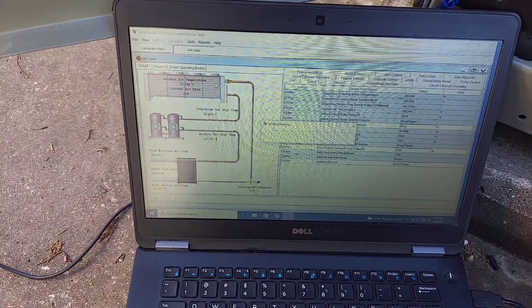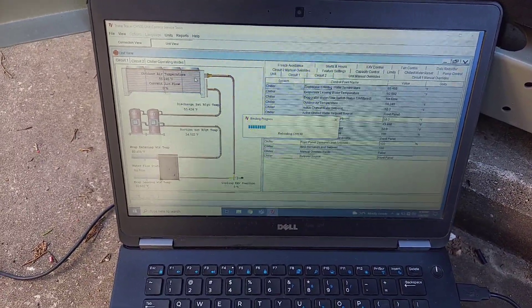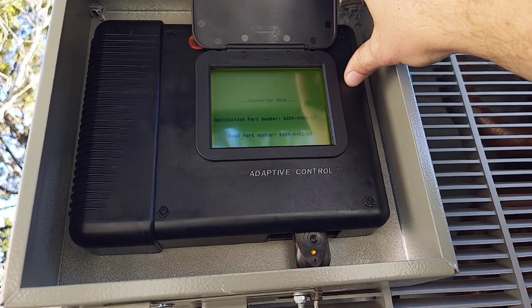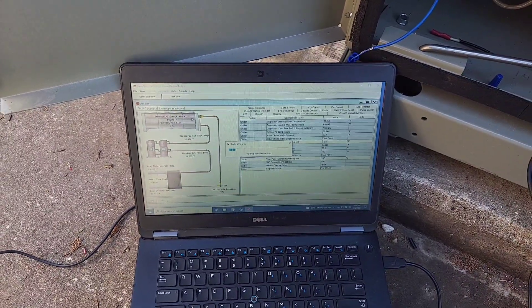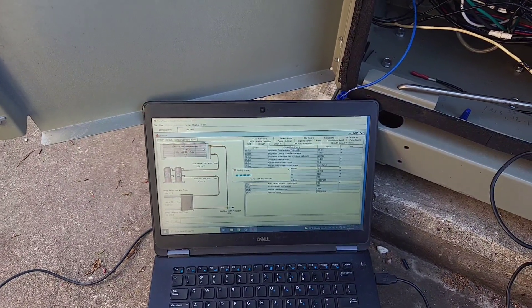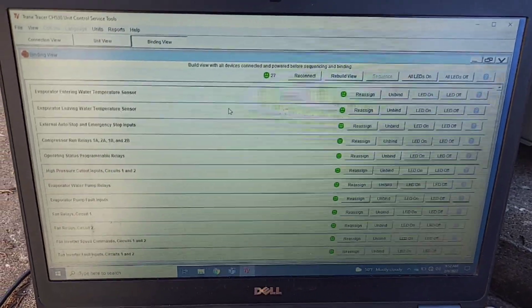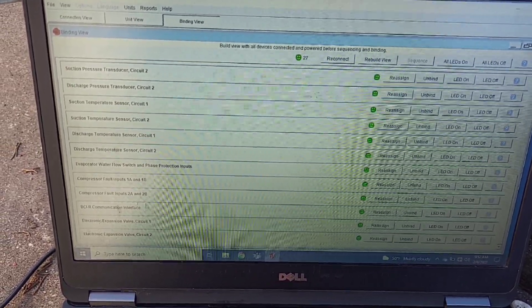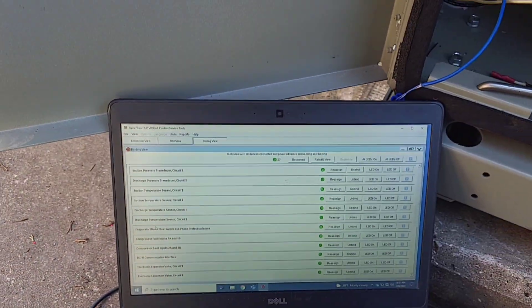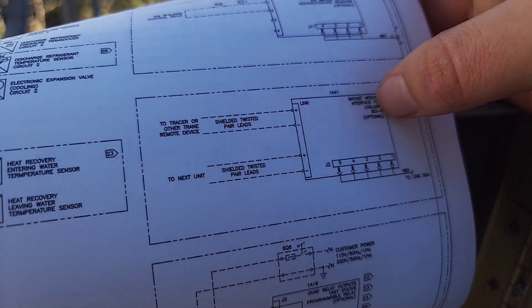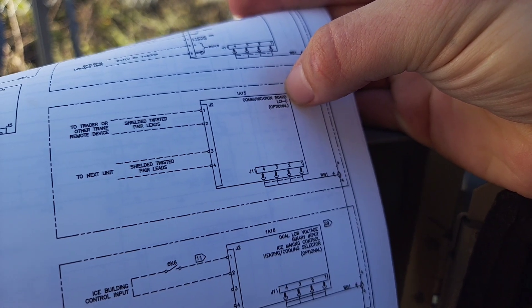I do have a full video specifically on how to go through a binding process on doing any kind of sensor or anything. At this point, the machine would be shutting down. It has to launch into a binding application. You're going to see your display will change into what they call the converter mode. It's going to take it a minute to fully go through everything, pull all the sensors, and see everything that is bound in this system. We're in the binding view. You can scroll through, we actually don't have an unbound device. So what that means is I got to go into the configurations on this programming and tell it that it's going to have that device.